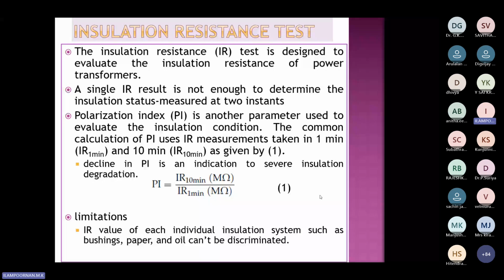Many people would have done electric circuits, right? So there is a transient current, and the transient current will be overcome. So they will measure at two conditions: one is 1-minute insulation resistance, another is 10-minute insulation resistance.